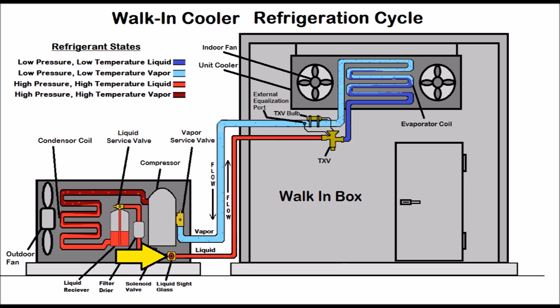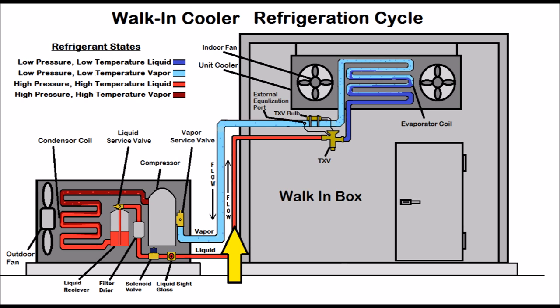Some outdoor units come with the liquid sight glass already there, but it's best to have it closer to the thermostatic expansion valve, right in front of it. As the sub-cooled liquid heads through the liquid sight glass, if you have a solid column of liquid it will be clear — unless there's an obstruction like a clogged filter dryer. It then heads into the thermostatic expansion valve as a high pressure, high temperature, sub-cooled liquid refrigerant. Going through the TXV, which is a metering device, it lowers in pressure and temperature and turns into a low pressure, low temperature liquid refrigerant.